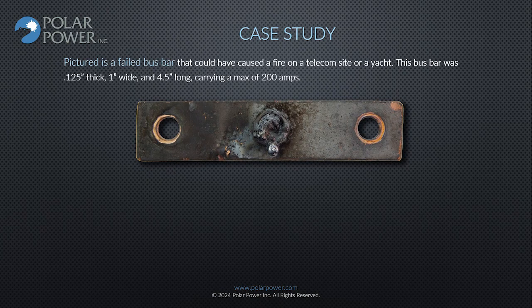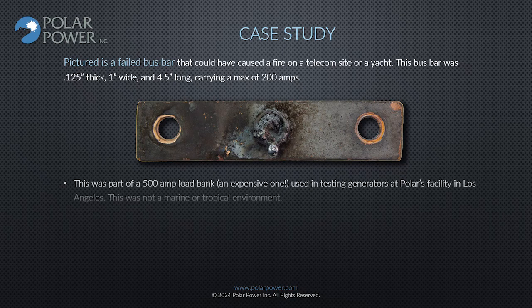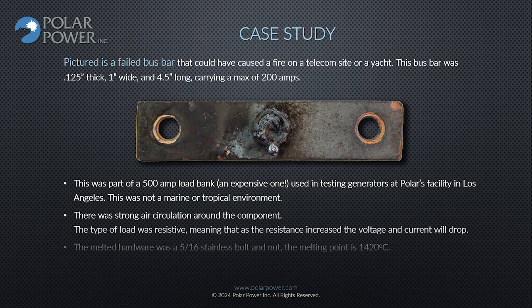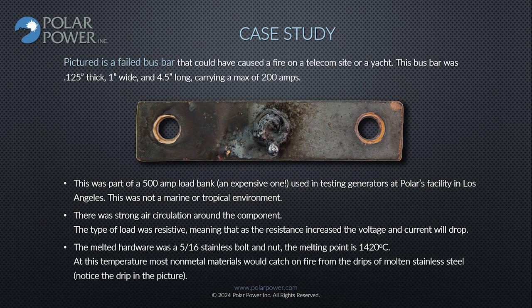And now, the case study. Pictured is a failed bus bar that could have caused a fire on a telecom site or a yacht. This bus bar was 1/8 of an inch thick, 1 inch wide, and 4.5 inches long, carrying a maximum of 200 amps. This was part of a 500 amp load bank, an expensive one, used in testing generators at Polar's facility in Los Angeles. This was not a marine or tropical environment. There was strong air circulation around the component.